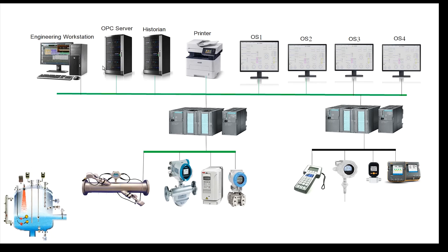SCADA normally comprises an engineering workstation where you have software to program SCADA screens, and you can also write scripts for specific processes. Then you might have an OPC server, which helps you connect to third-party devices. You also have historians to store historical data — so you can look back years at process variables. There's also a printer for trends and mimics, and operator stations where operators visualize information coming from the process.